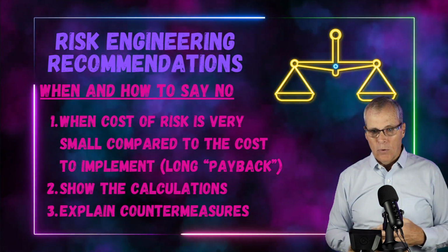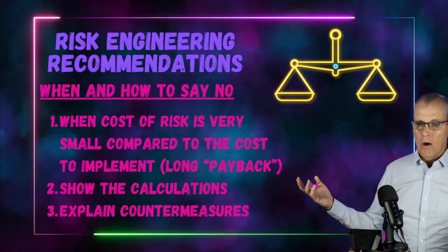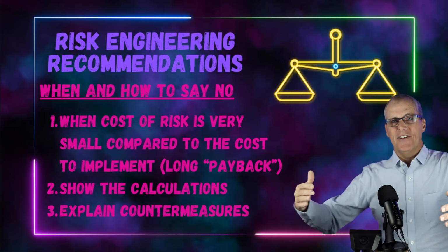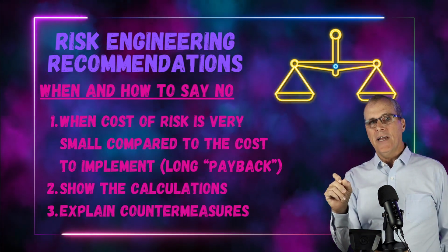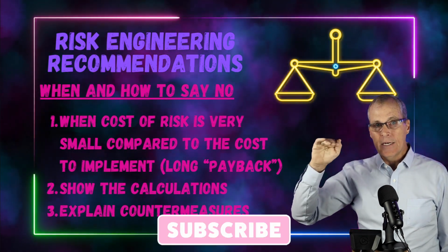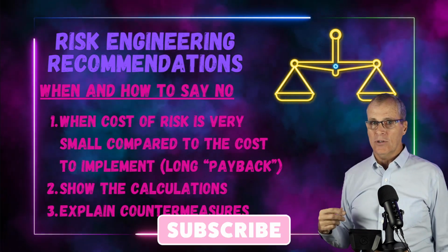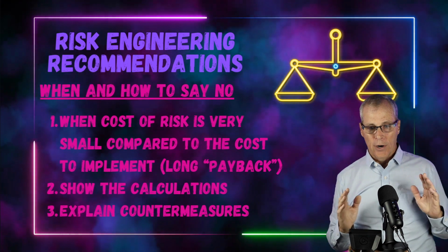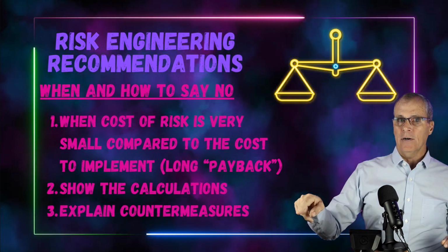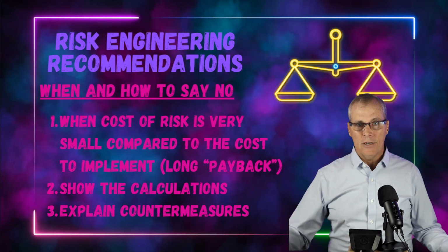So it really boils down to, if we made that deep well pump start automatically on a 6 million gallon tank, right, that only needs 1 million gallons for fire protection, we've got 5 million gallons of water before we even start dipping into the fire protection water. And you want the deep well pumps to start so we don't run out of water, when we're only going to be flowing water through one or two heads in a service building fire, in an office building, or they're not going to get flowed at all because the hydrants won't get used.